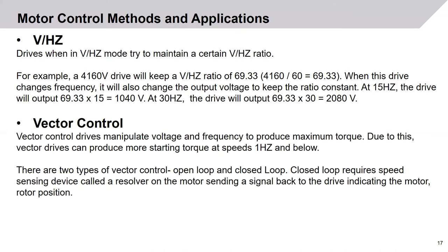Motor control methods and applications: volts per hertz control and vector control. When drives are in volts per hertz mode, they maintain a certain volts per hertz ratio. For example, a 4160-volt drive will keep a volts per hertz ratio of 69.33 (4160 ÷ 60 = 69.33). When this drive changes frequency, it also changes the output voltage to keep the ratio constant. At 15 hertz, the drive outputs 69.33 × 15 = 1,040 volts. At 30 hertz, 69.33 × 30 = 2,080 volts. At 60 hertz, 69.33 × 60 = 4,160 volts.